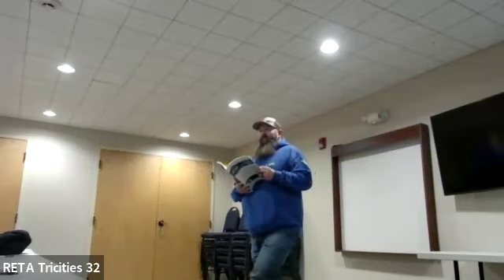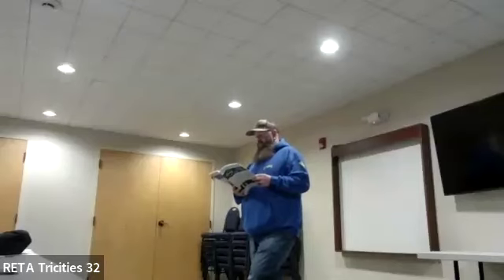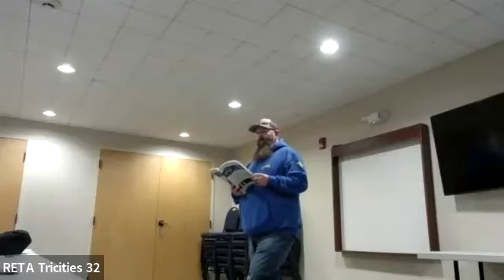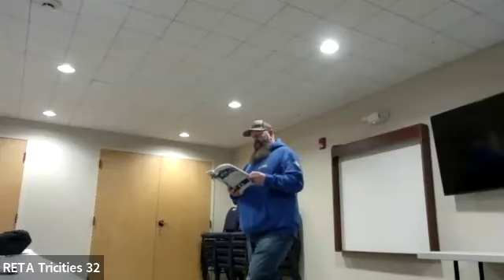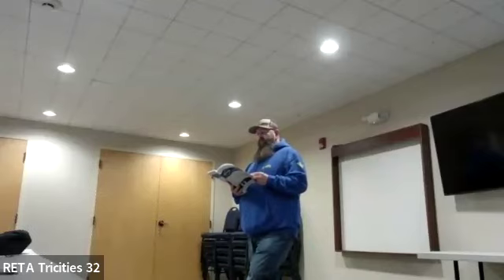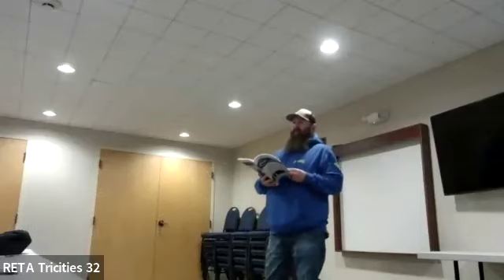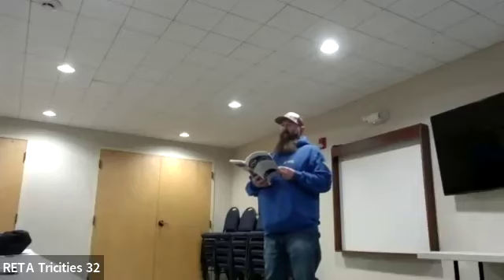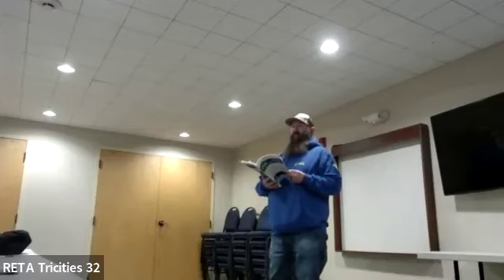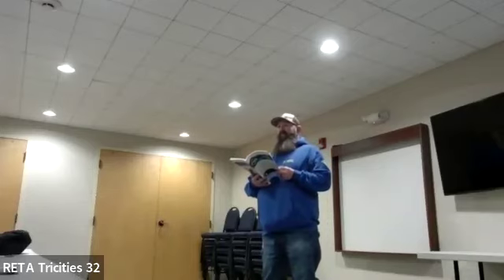So for us, we do a lot more pump outs than most people. The ammonia-rated hoses that you buy from whatever supplier that are stamped, as Josh is saying, are designed for ammonia. The moment they come in contact with oil, they begin to soften. We learned of this a couple years ago, and we're watching for it much more now. We've not had a release, but we've taken hoses out of service because they were softened or blistered or split on the inside. None of us ever realized that the hose wasn't compatible with oil.